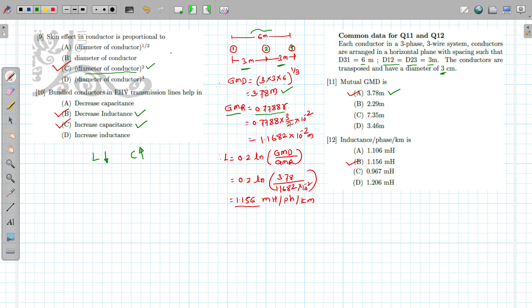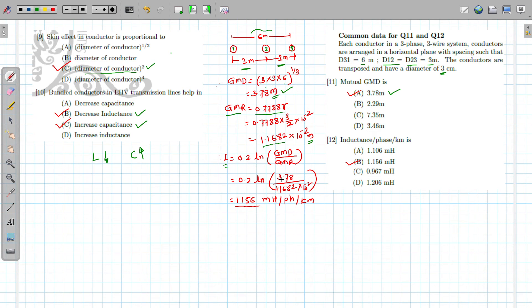GMR = 0.7788 × r. The diameter is 3 cm, so radius = 1.5 cm. Calculating the effective GMR gives 1.1682 × 10⁻² m. The inductance formula is L = 0.2 ln(GMD/GMR). Substituting GMD = 3.78 m and GMR = 1.1682 × 10⁻² m gives L = 1.156 mH per phase per km. The second option is correct.